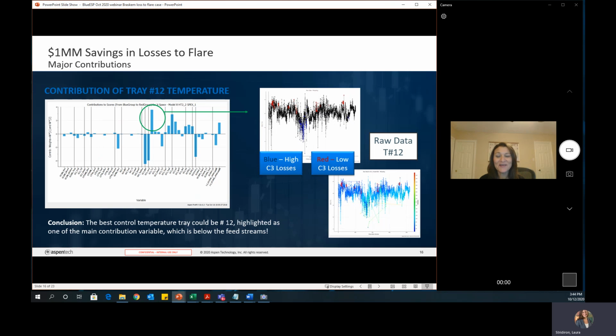So in summary, based on this analysis from ProMV, Braskem determined that using the tray temperature indication above the feed stream was not the appropriate variable for controlling reboiler steam flow, and that the tray 12 temperature below the feed stream should be used instead.